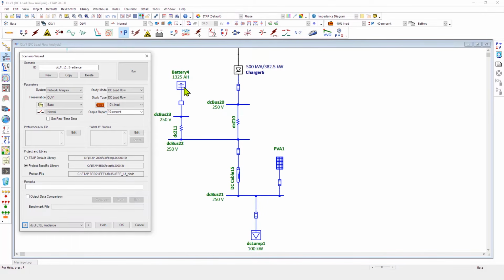and observe the effect on the battery charge and discharge, as well as the contribution from the battery rectifier or the battery charger. First up is the case of 10% irradiance. We can observe the current and the voltage as well as the contribution from the battery, which is trying to compensate for the reduced power output from the PV array. We can also see contribution coming in from the rectifier into the DC system.